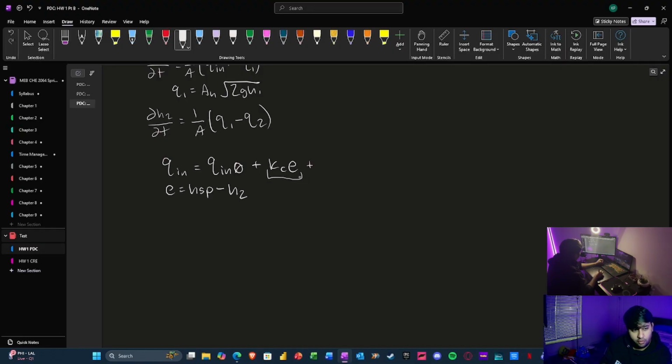And this is actually called proportional offset. And this is only due to the fact that we have only a proportional controller. We don't really have an integral controller to balance that out. And that's one of the reasons why we didn't reach our set point in part A. It's because we didn't have an integral controller to eliminate this offset. So we're going to be applying that today.